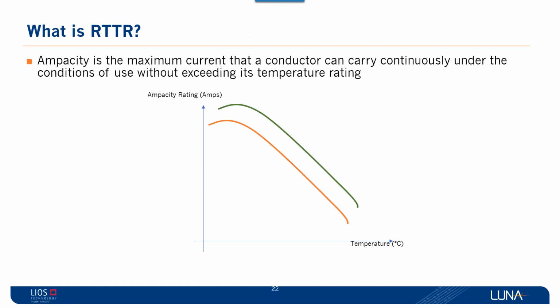What is RTTR, or what we call real-time thermal rating? If you have a maximum current passing through the conductor, you are limited by the temperature of the dielectric that's used to build the power cable. What it simply means is that as the temperature is increasing, you're losing your ampacity rating. So in the steam line situation that was presented earlier, that was the case. Every time there is a steam line, the temperature goes up. You're affecting the duct bank, you're affecting all your circuits, and strategically, even the circuits that are closer to the steam line.